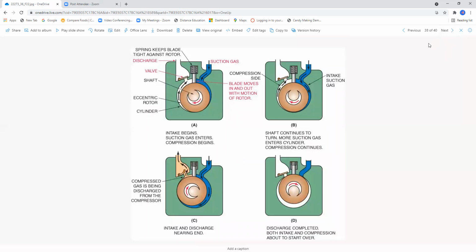Okay, this illustration is on page 1074 of your textbook under 36.22. This basically shows how the stationary vane of a rotary compressor works. In this illustration, the refrigerant enters at this point, and notice that the valve is closed here. We have a slider valve here, so the refrigerant is going through this eccentric rotary compressor. And we come down to C, notice that the refrigerant is still blocked at this point, coming through here, being compressed. Eventually it blocks off the suction port and opens up this side. And of course, the discharge gas now has increased pressure and increased temperature, so it goes into the condenser where it gives up the heat which was absorbed in the evaporator coil.